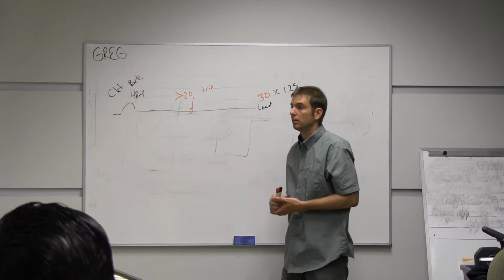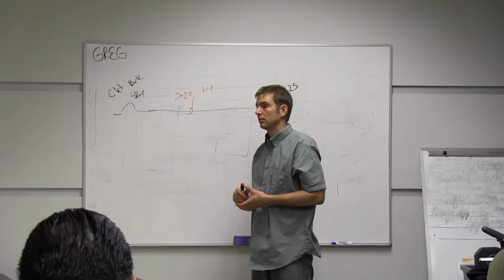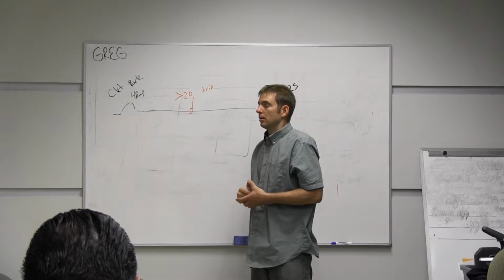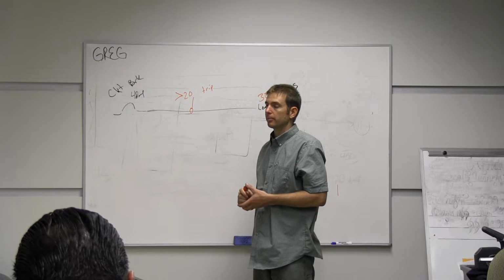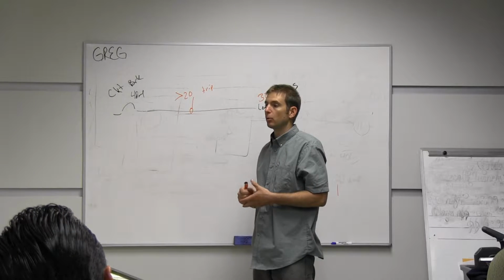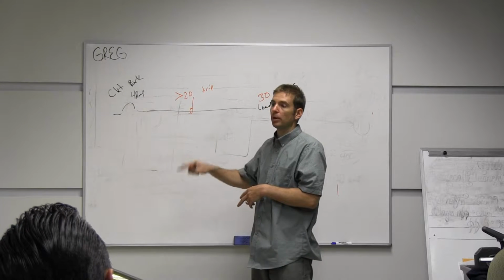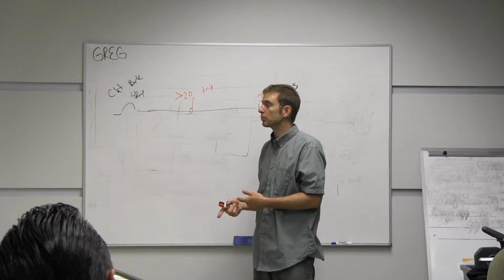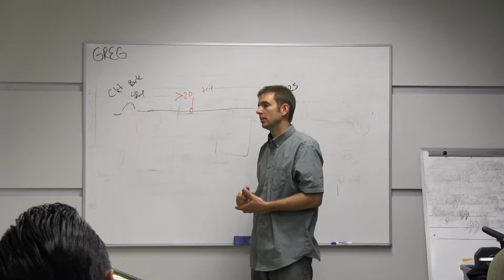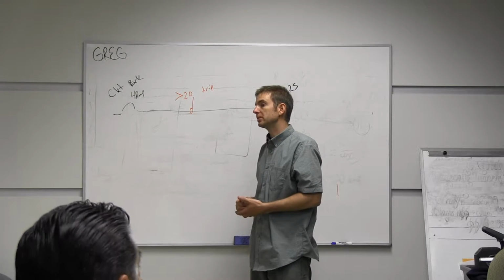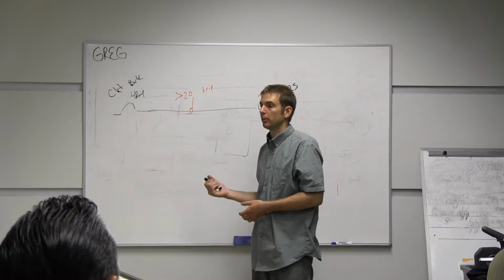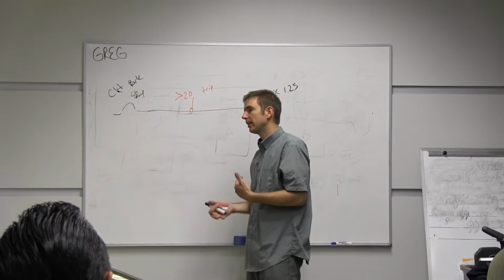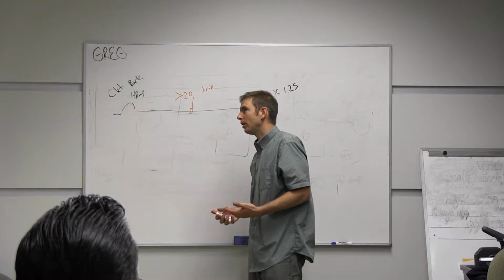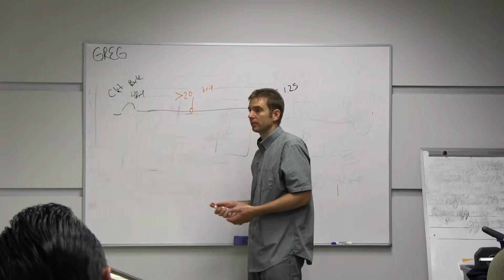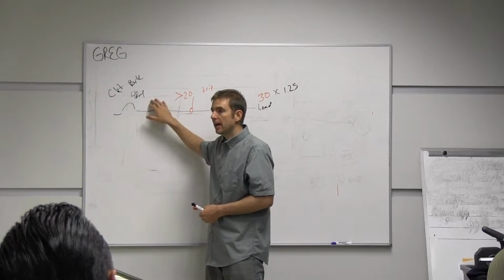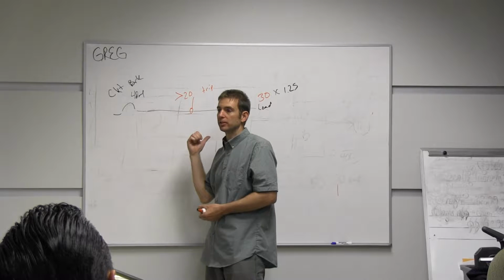Is there any easy way to test the breaker to see if it's functioning properly or when it breaks down? If you suspect that your breaker is tripping because you have a weak breaker, you can replace it with the one that you had just purchased or one that you know is working, and take your breaker and get it tested. But if the new breaker you replaced it with does not trip, I would just throw the other one away. A 40 amp breaker, depending on the panel type, could cost you $12 to a couple $100. So depending on what type of breaker you have, you might just throw it in the garbage because it's not worth driving to a place to get it tested.